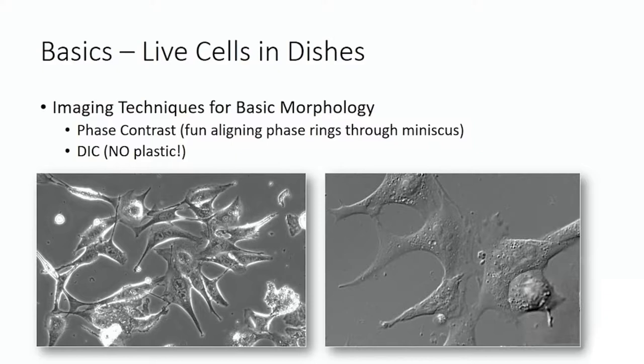If you've got live cells in dishes that are not stained and you want to look at them, phase contrast is the way of choice. But on my confocal scopes I don't have phase lenses — I have DIC lenses, so I can do it with DIC. But you can't do DIC through plastic. So if you've got a plastic lid, you can't do DIC — it won't work. You have to know that in advance.